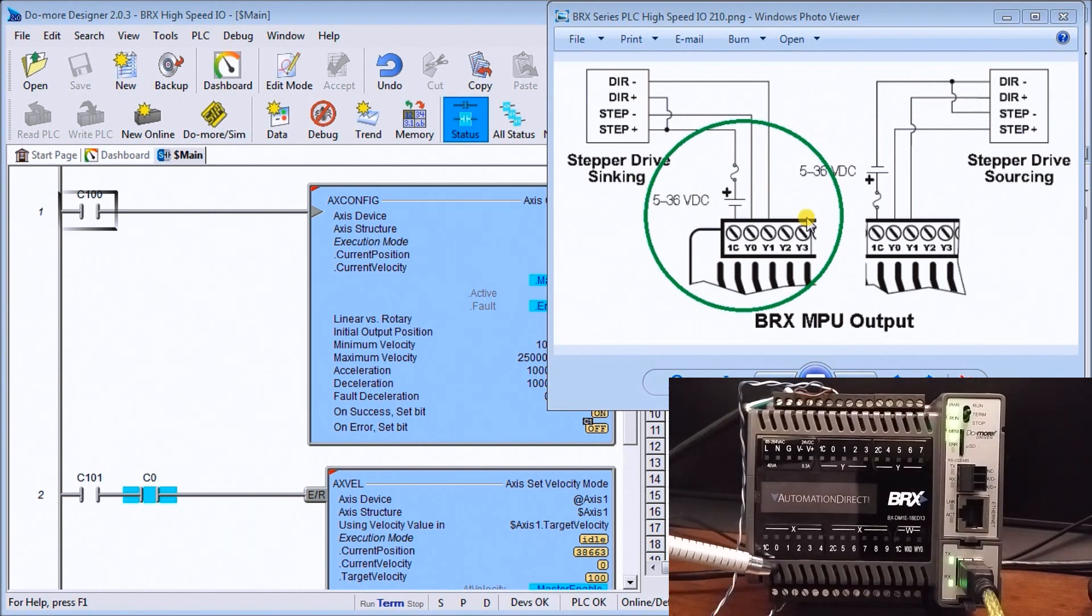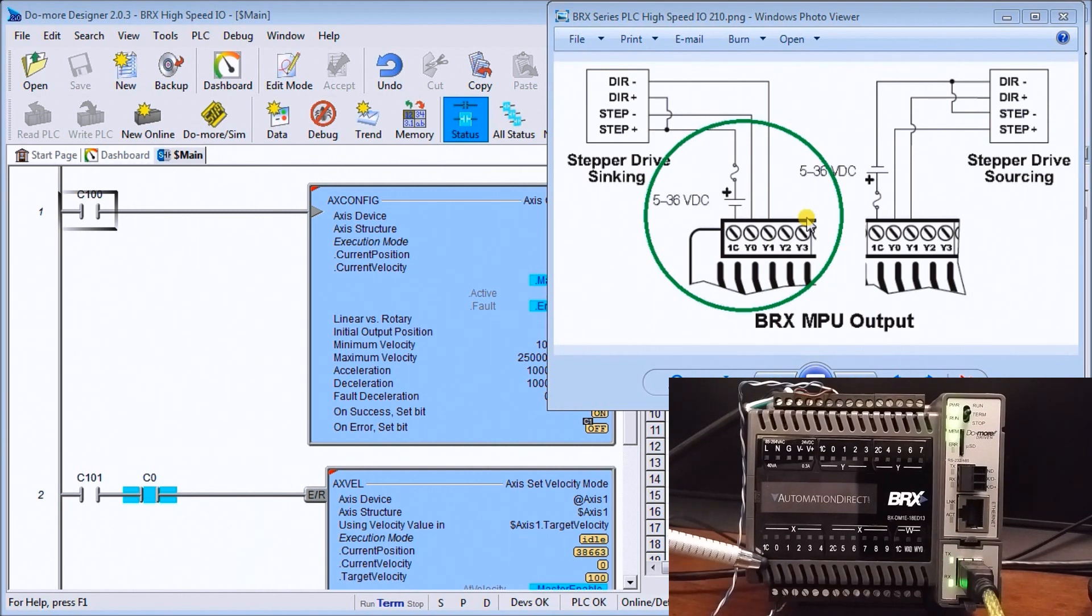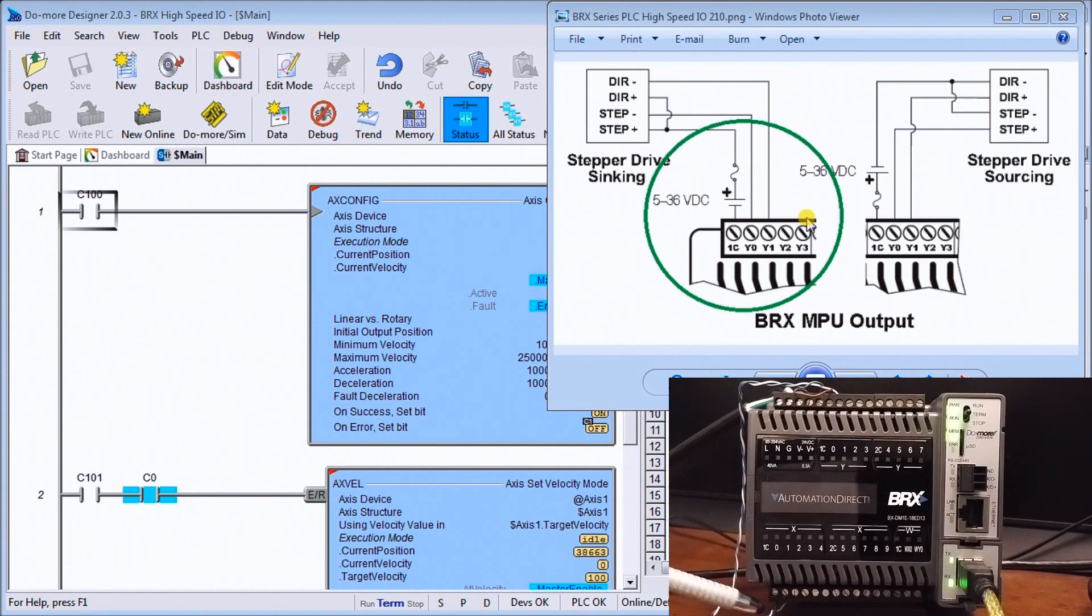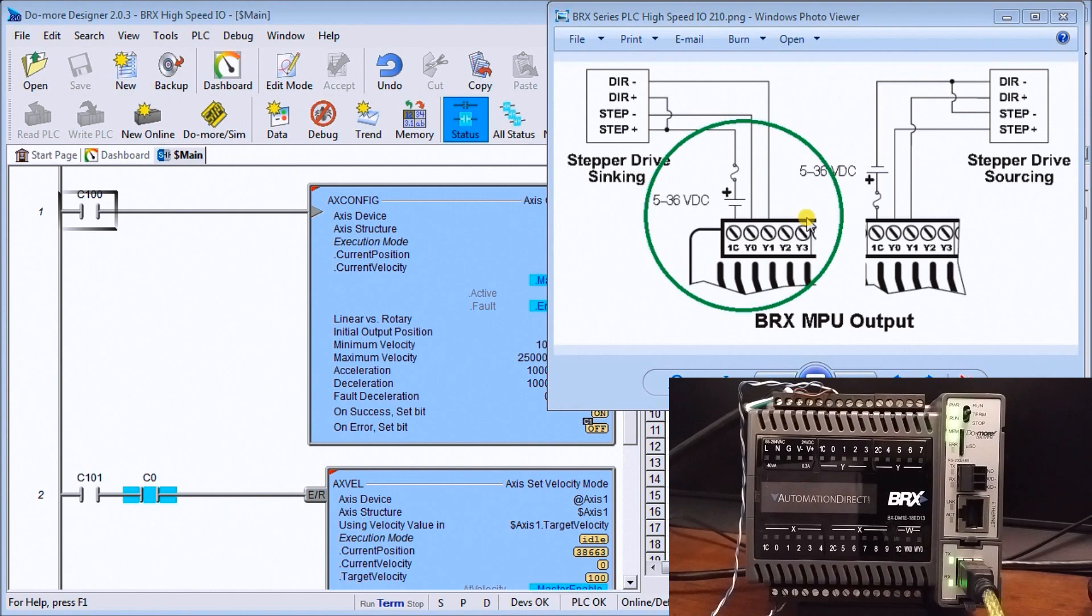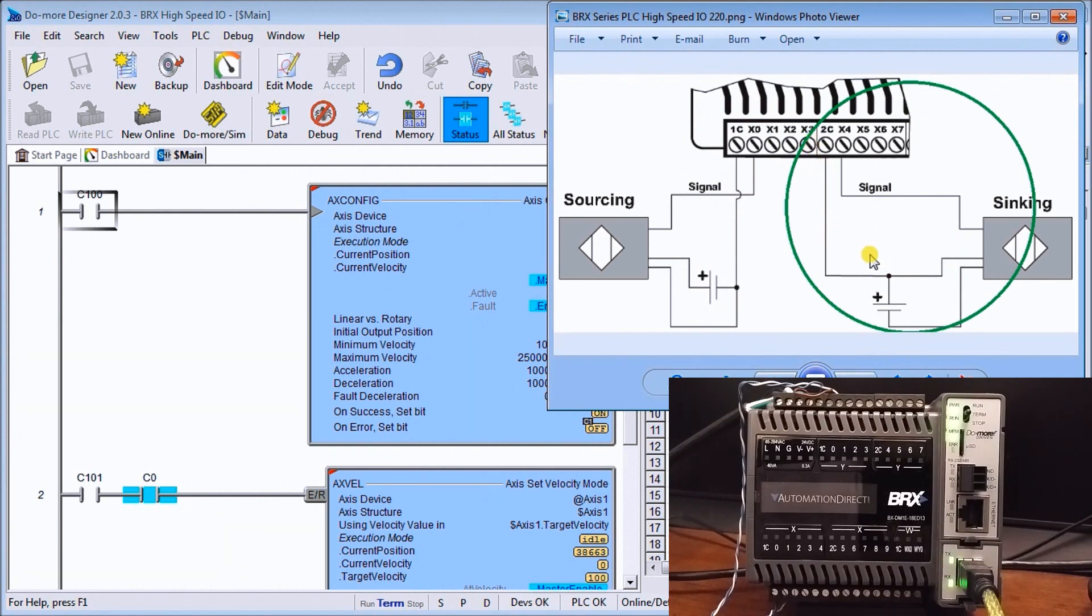Our output side of the output will then go into our first input which is x0 and then a common of this will then go from our common back into our power supply at 24 volts. So what you'll see is we actually have our output is a sinking and our input is also a sinking because we have the common sitting at plus 24.